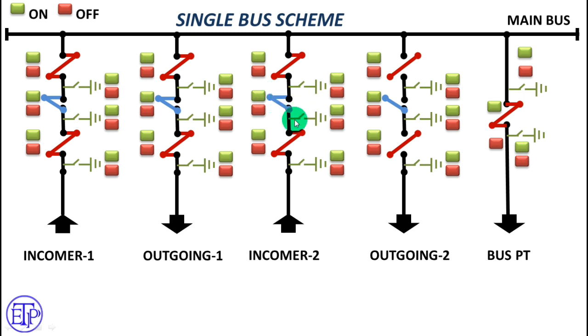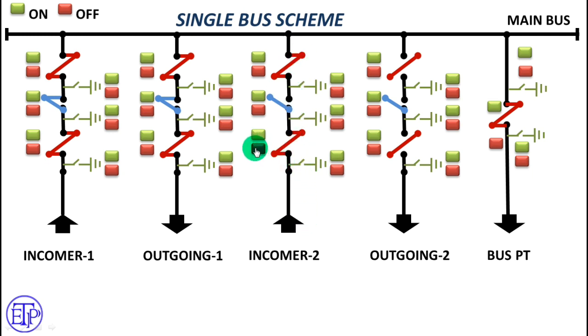Now suppose we have to take this breaker into maintenance. How will the isolator be operated? First we have to open this circuit breaker, because this incomer is now carrying current — so I cannot open this isolator directly. I have to first open this circuit breaker. Pressing the red button, the circuit breaker is opened. Since the circuit breaker has opened, this path is not carrying any more current. Now we can open this isolator, thus isolating this incomer. For the bus PT, if I need to take it into maintenance, I can just open this isolator because the bus PT draws only a very small magnetizing current which can be broken by the isolator.